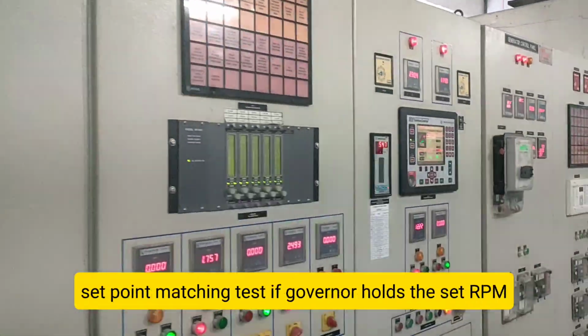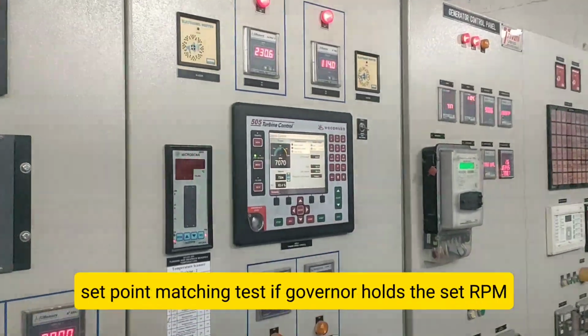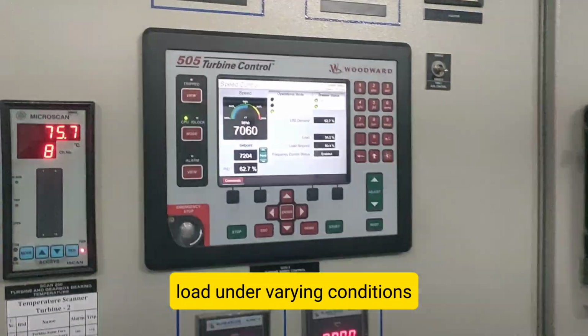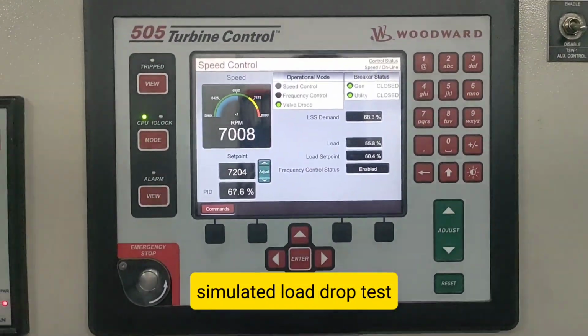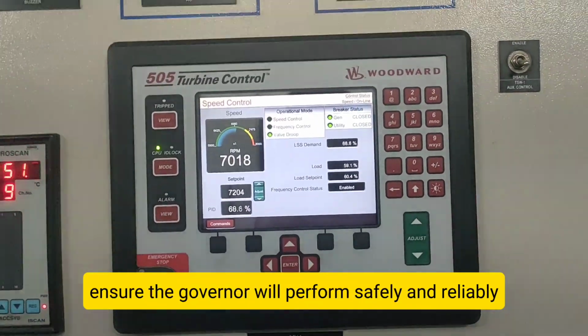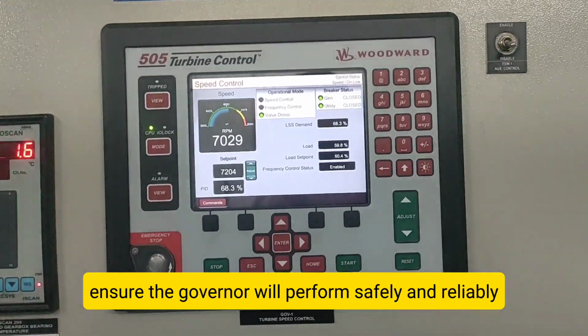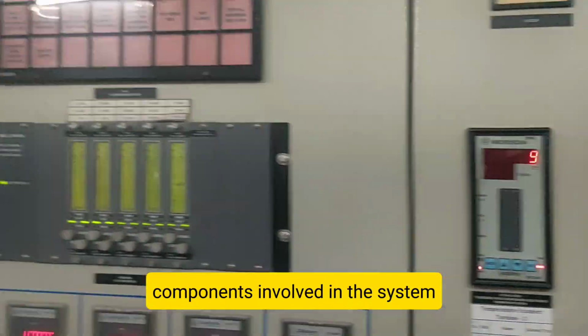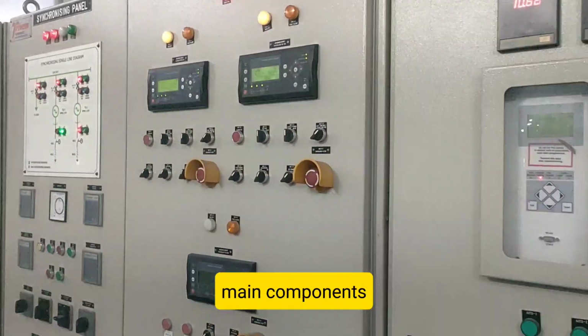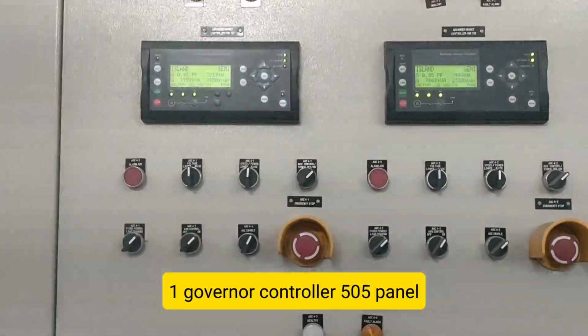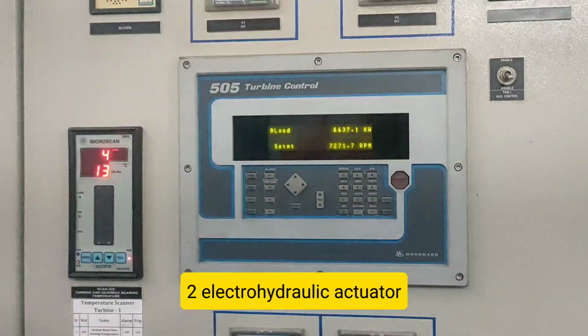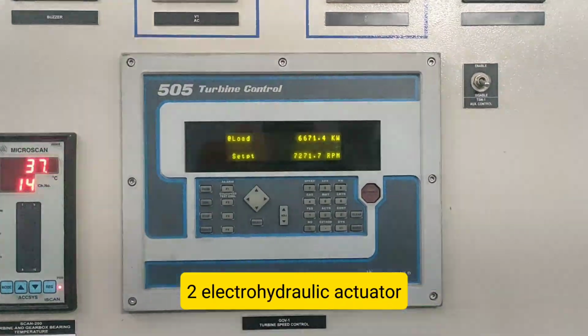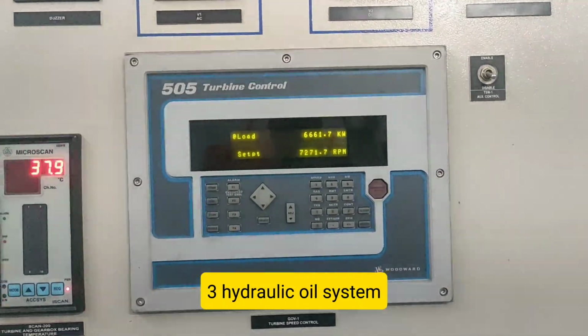Safety features of 505 Governor. The 505 Governor is equipped with multiple safety systems: overspeed trip protection, high exhaust temperature protection, steam pressure limiters, and shutdown on oil pressure loss. It can communicate with emergency stop valves, ESV, and trip solenoids to shut down the turbine safely.